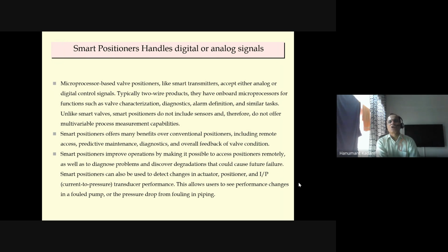Smart positioners handle a digital or analog signal. So here we have seen HART, if it is there, it handles analog signal and digital also. So microprocessor based valve positioners, like a smart transmitter, accept either analog or digital control signal. Typically two wire products, as you have seen the smart transmitter, two wires. They have onboard microprocessor. We have seen the microprocessor, transmitter, CPU board, input sensor board, and display board also. So there you have seen they have onboard microprocessor for functions such as valve characterization, diagnostics, alarm definitions, and similar tasks. So on the microprocessor, you will get these functions.